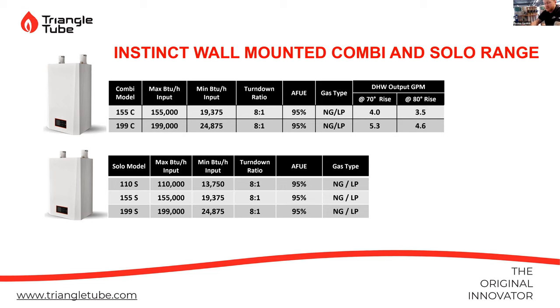And then on our current solo heat only models, we have a 110, a 155, and a 199. Same specs, but on those boilers, they do not include the system pump right now. Once we come out, I think at the end of next year, we'll be having a V2 series on the boiler. All of our boilers will have system pumps installed. But just understand the heating only, you'll have to provide that pump. Pros and cons. One is most guys prefer to have that in there. They just throw the boiler in, call it a day. Some guys, and I'm kind of in this camp, I like not having the system pump. That way I can size that pump according to my output and according to my design. So I have a little bit of flexibility there on what my GPM is out of that boiler.